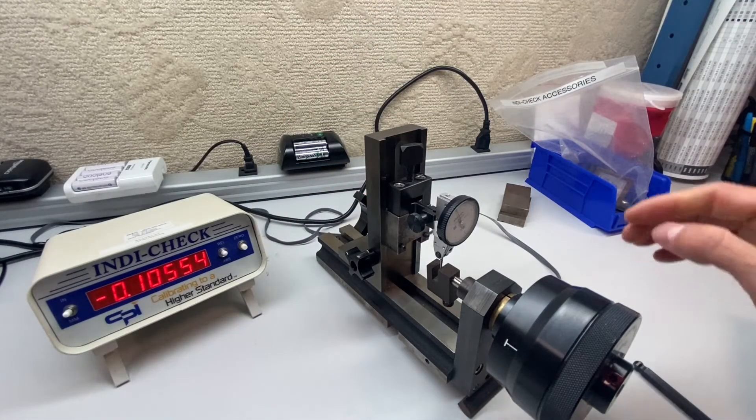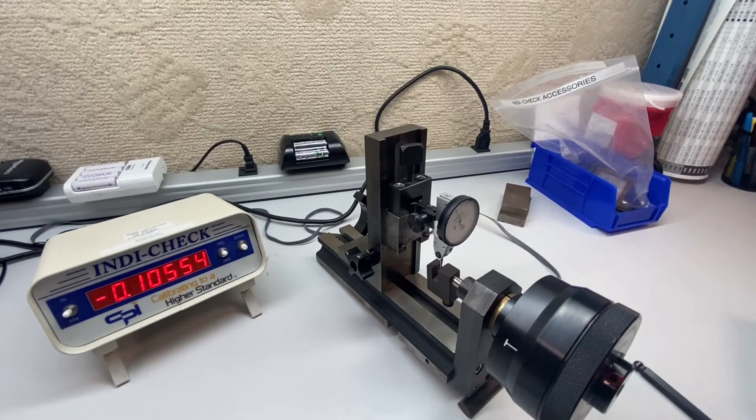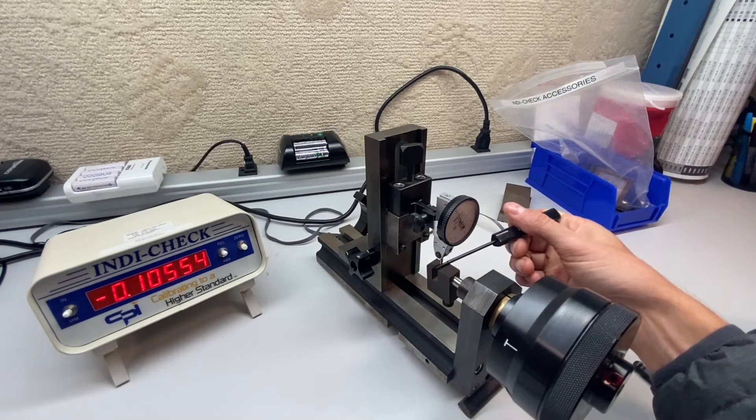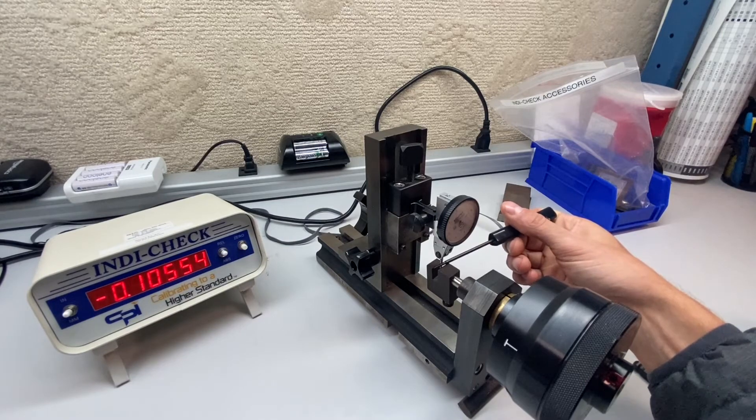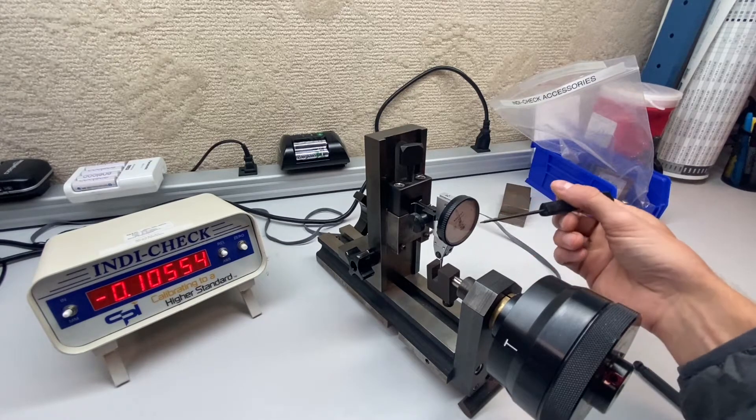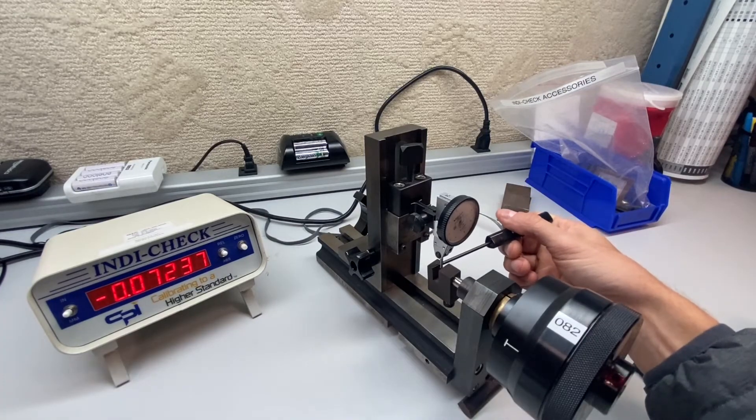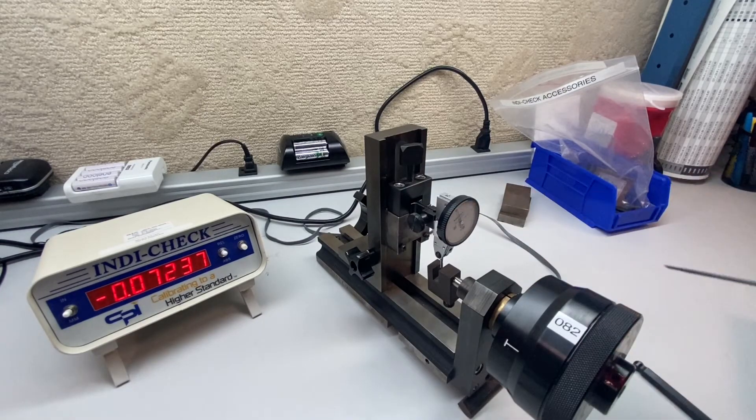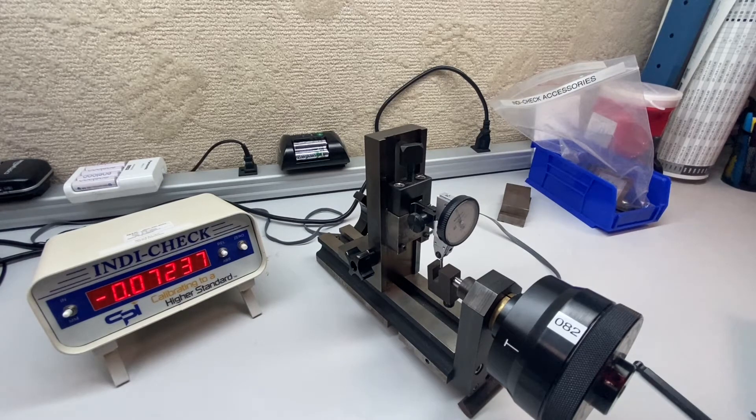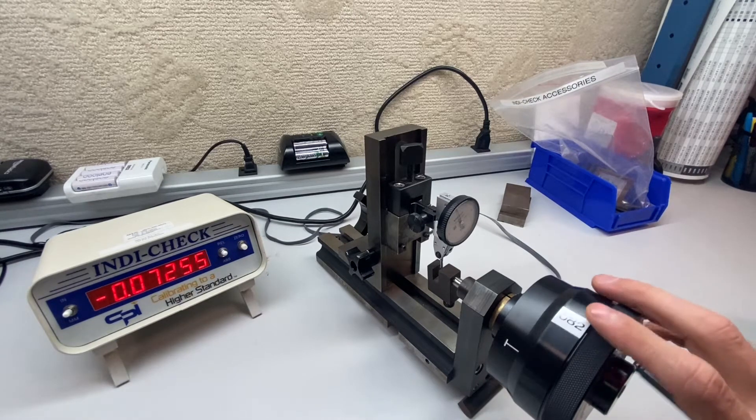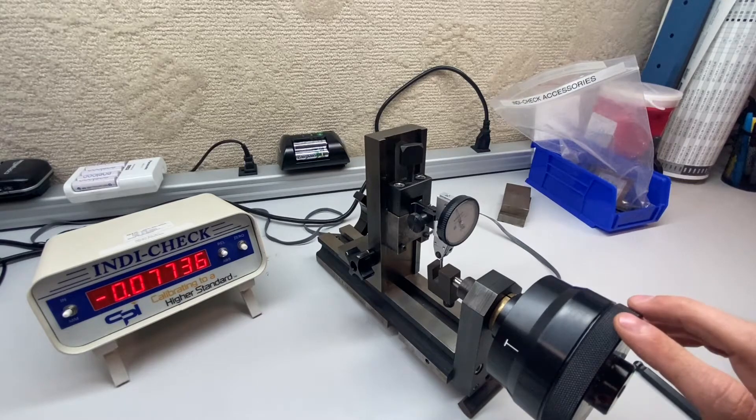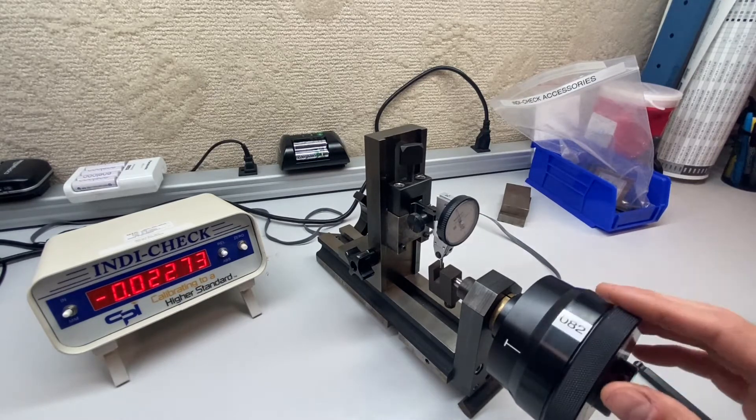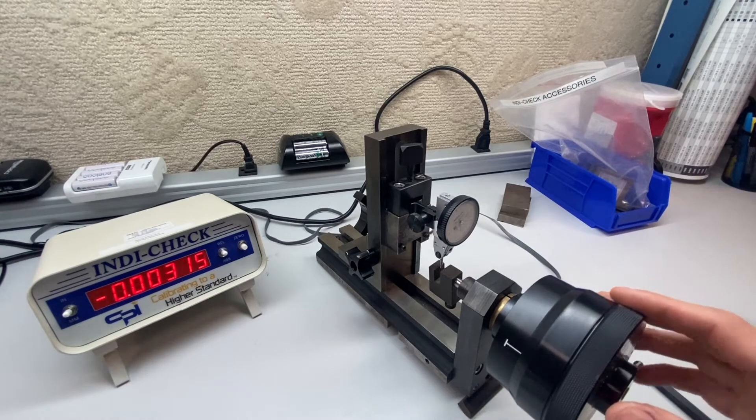So these test indicators you can measure in both directions. Backwards if you push on that tip it measures, and forwards if you pull on the tip it'll measure. So we've got to check both. We've got to do hysteresis, so some repeat in both directions. You're going to go all the way back and then come back to zero, and then come all the way forward and then come back to zero.